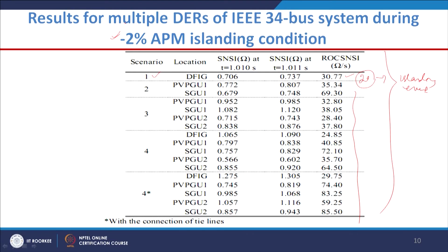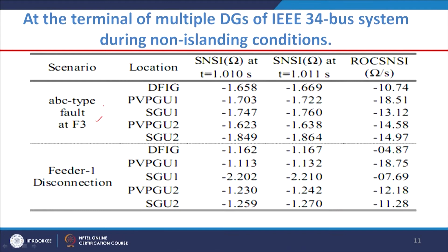These results were obtained for −2% active power mismatch (APM). We also tested non-islanding events on the IEEE 34-bus system, including an ABC-type fault at location F3 and feeder disconnection, considering different DG types: DFIG (wind system), PV system, and synchronous-based DG. Different types of renewable sources were included to test the technique's robustness.